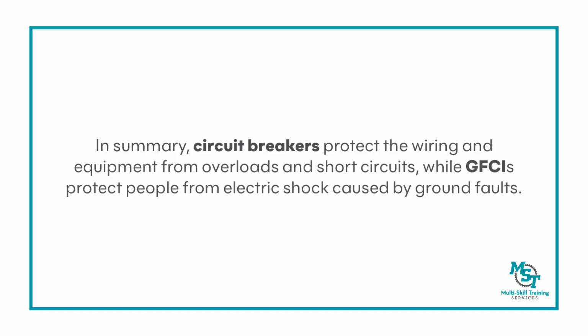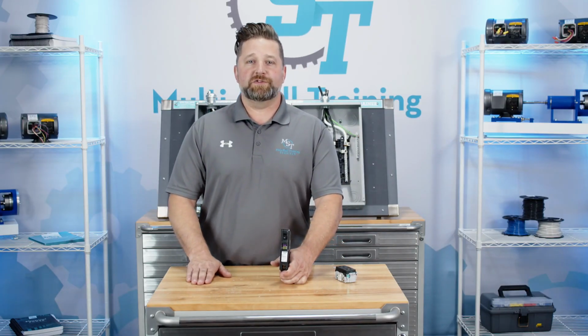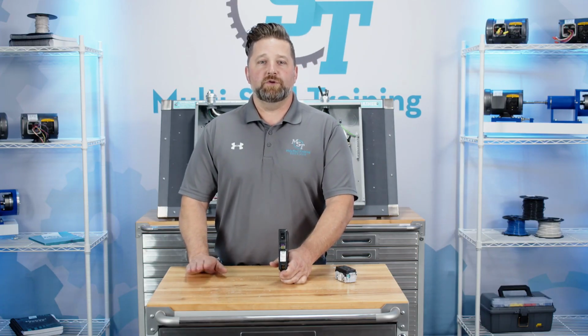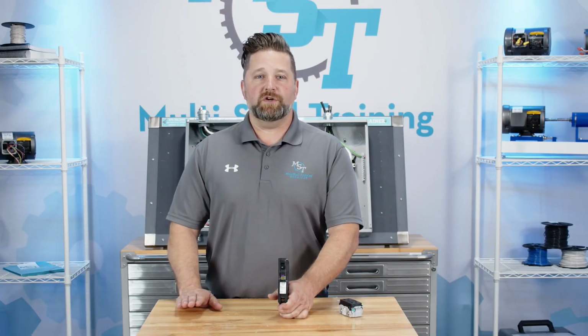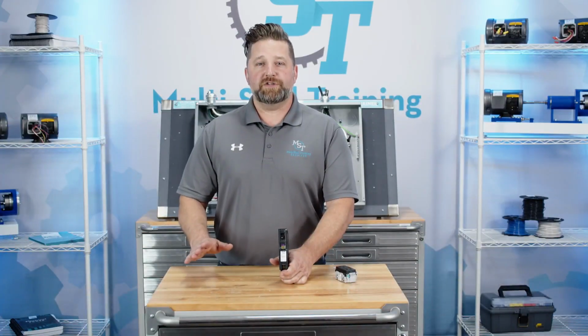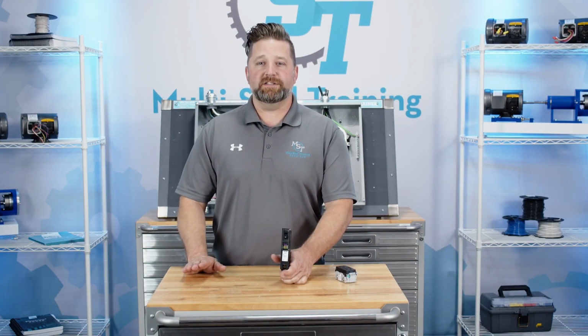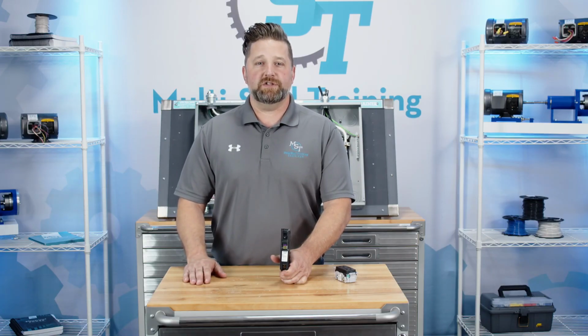So in summary, circuit breakers protect the wiring and equipment from overloads and short circuits, while GFCIs protect people from electric shock caused by ground faults. Both devices are essential for electrical safety, but they work in very different ways to achieve that safety. Technicians should also be aware that GFCI protection can be provided either at the outlet level with the GFCI receptacle or at the panel level with GFCI breakers. Understanding the roles and differences between these protective devices is critical for industrial maintenance technicians who install, troubleshoot, and maintain electrical systems in both industrial and commercial environments.